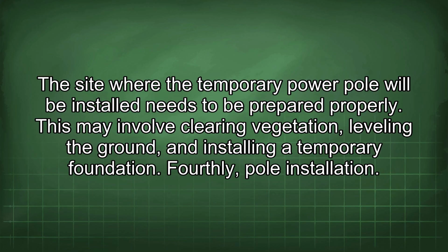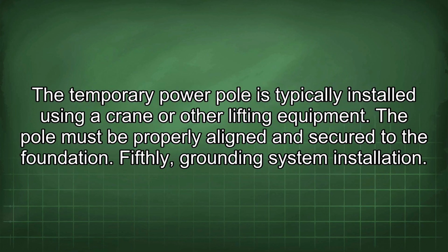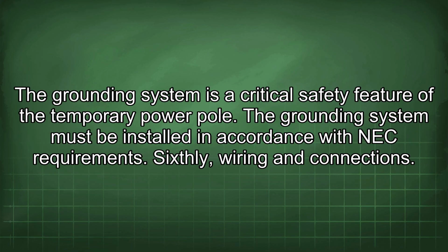Fourthly, pole installation. The temporary power pole is typically installed using a crane or other lifting equipment. The pole must be properly aligned and secured to the foundation. Fifthly, grounding system installation. The grounding system is a critical safety feature of the temporary power pole. The grounding system must be installed in accordance with NEC requirements.